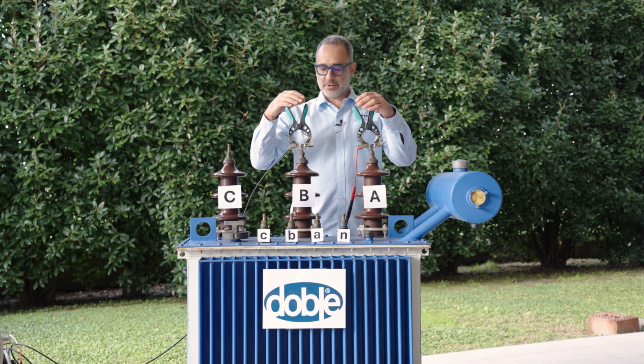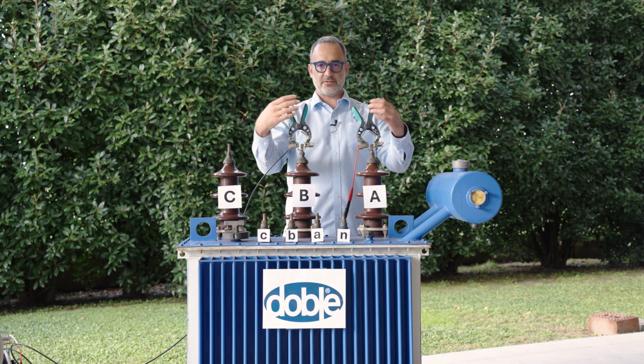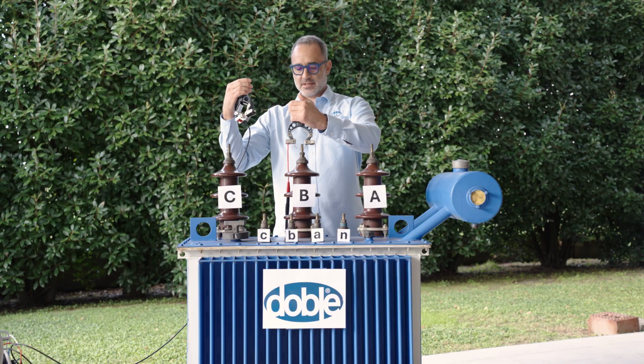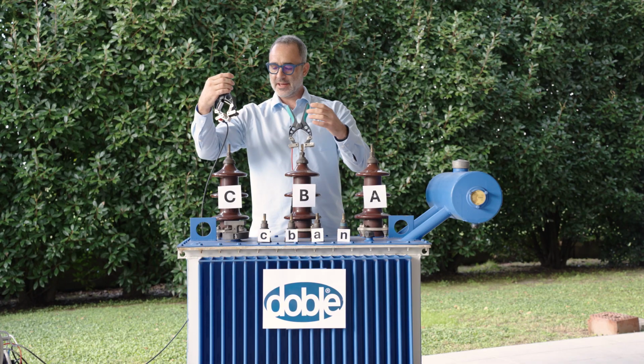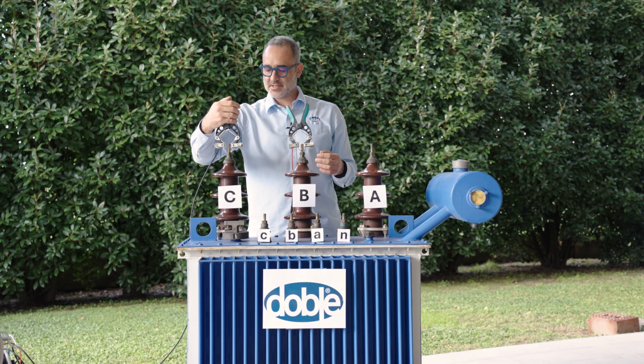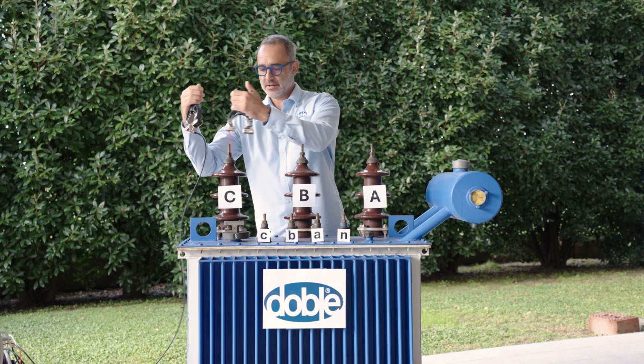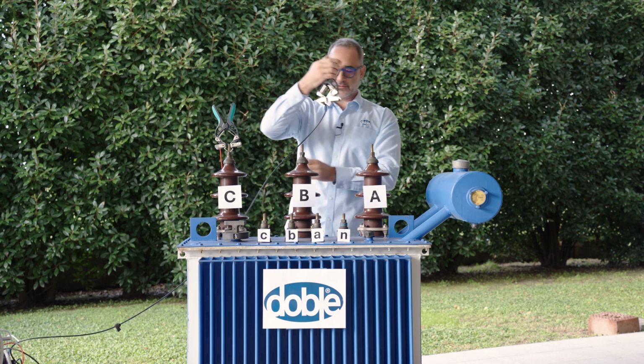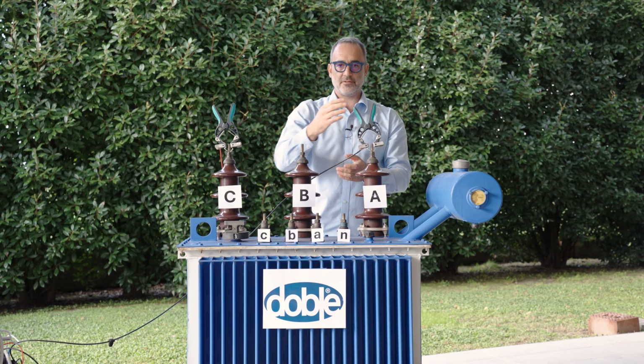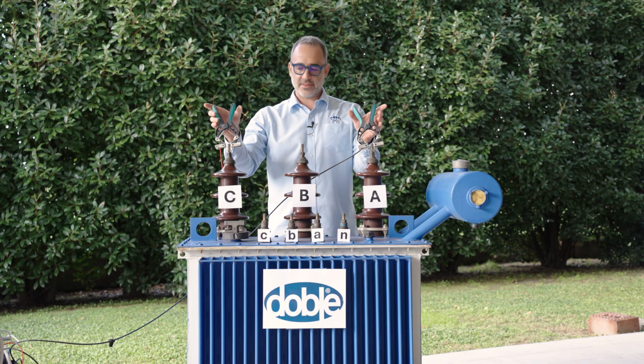So the first test will be done generating on phase A, measuring on phase B. The second test will be done generating on phase B, measuring on phase C. And the third test will be done generating on phase C and measuring on phase A. So we need to do 3 tests.